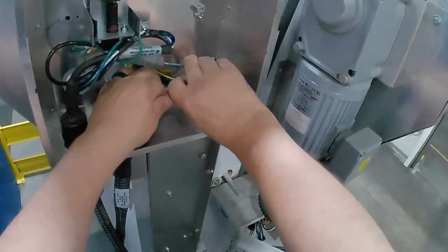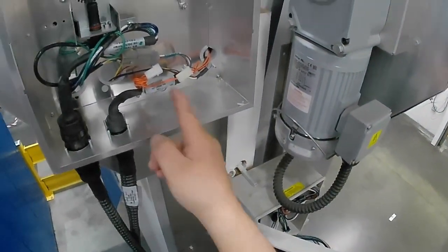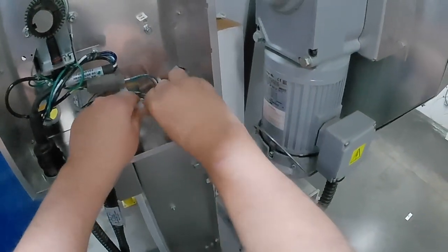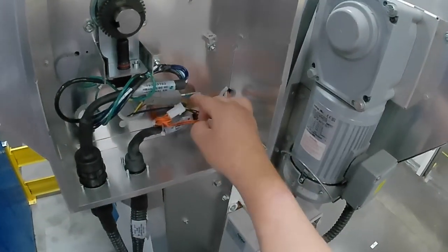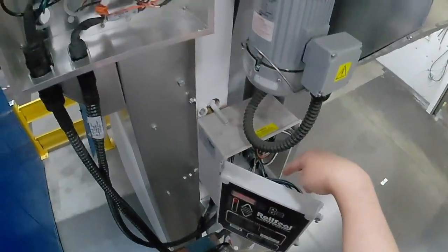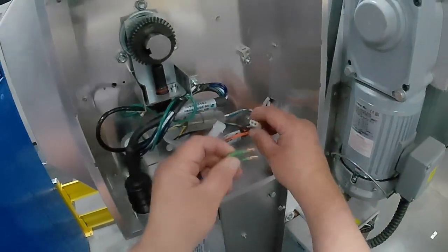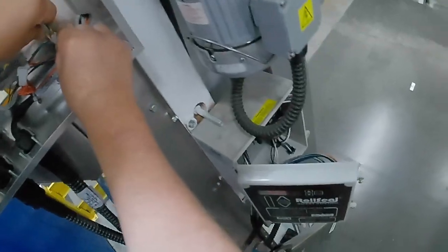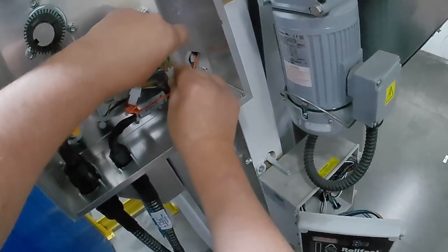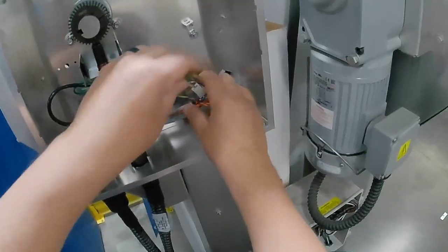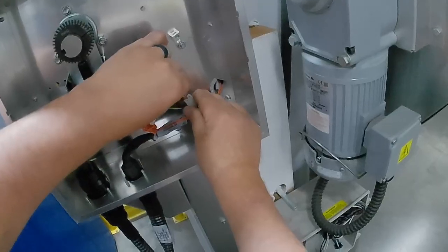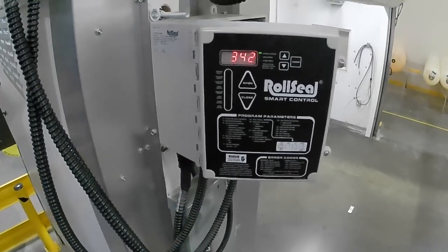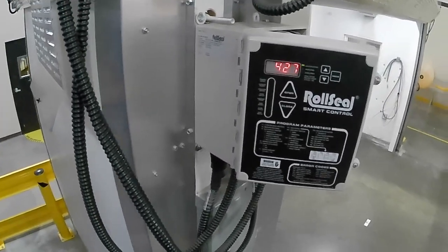I opened the connector and it had no effect. If that had no effect, I don't know whether it's supposed to be closed or open. So I said, well, hey, what the heck? Here is the portion of the connector that goes back to the controller. So I created this little jumper, and as soon as I jumpered out this switch, boom, the noise stopped, everything went back to normal. Everybody's happy, boys, everybody's happy. So we need to find out how to get to that switch, fellas. So bada bing, bada boom, we found our problem. Now, how to fix the problem, I don't know yet.